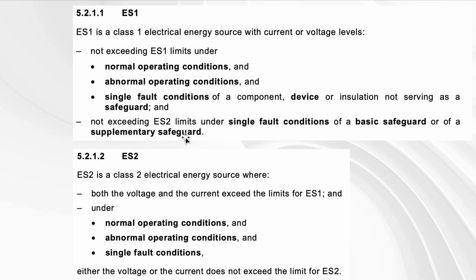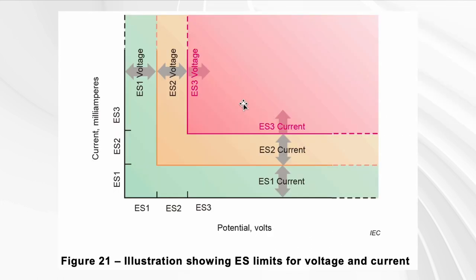If there's a single fault condition of a basic safeguard or of a supplementary safeguard, then it must not exceed ES2. This is already a pretty bad situation. If it exceeds ES2, it is ES3 — and ES3 is really the red area you want to avoid.